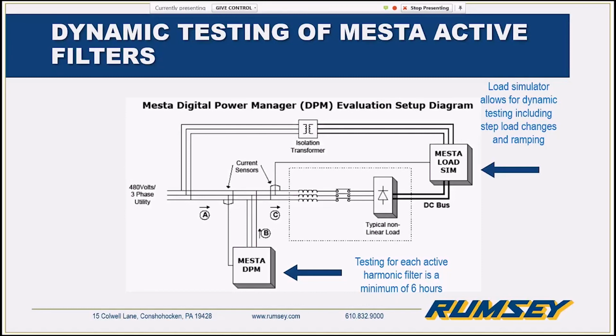Additionally, with this testing, we do current limit all of our equipment. So all of it's designed to say, if I'm a 100 amp filter, it'll output only 100 amps of correction. If loads are added later on, and now there's 110 amps of harmonic distortion out there, the active filter will just provide 100 amps, and it won't cause any problems to the filter.